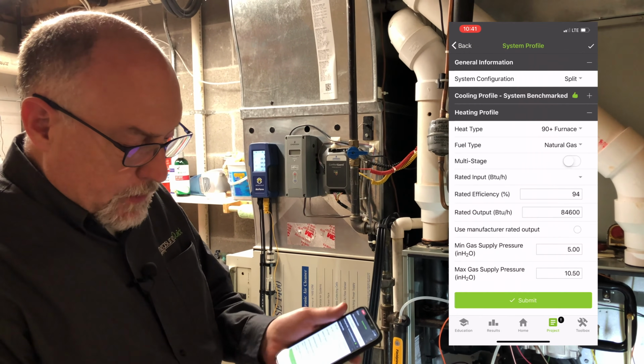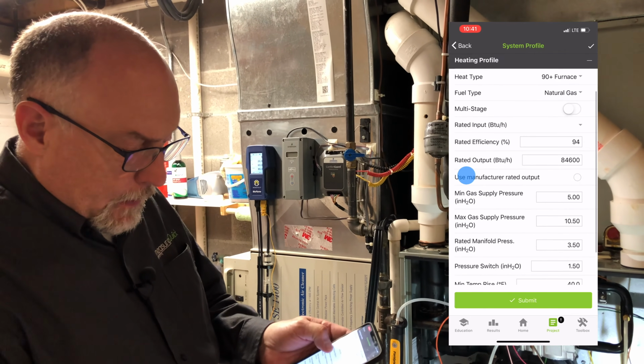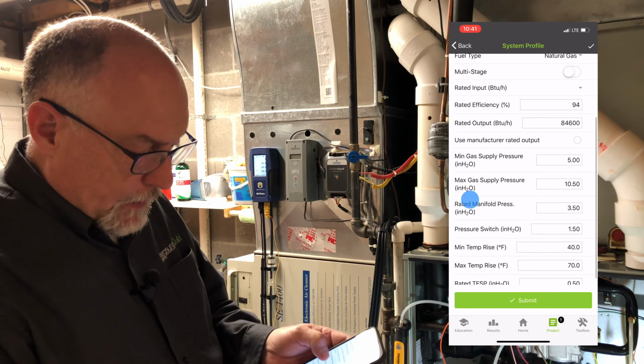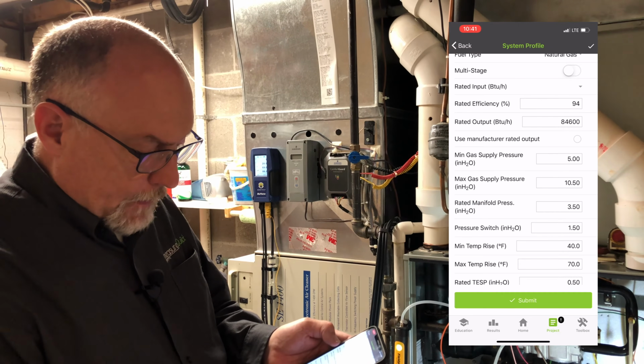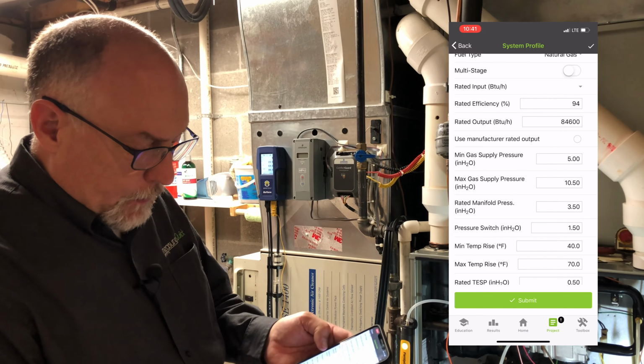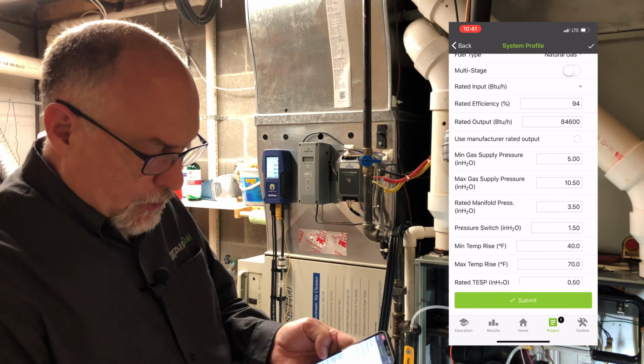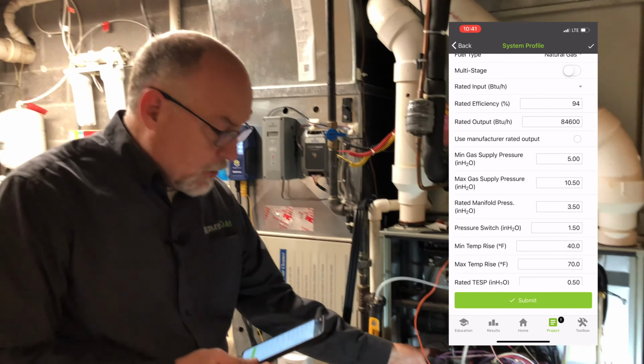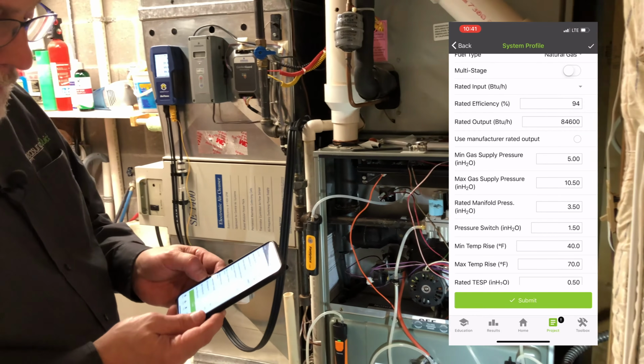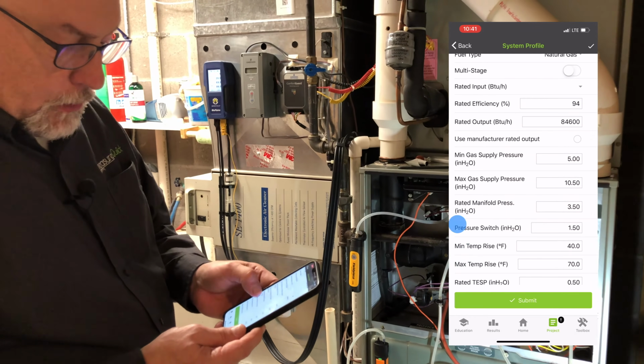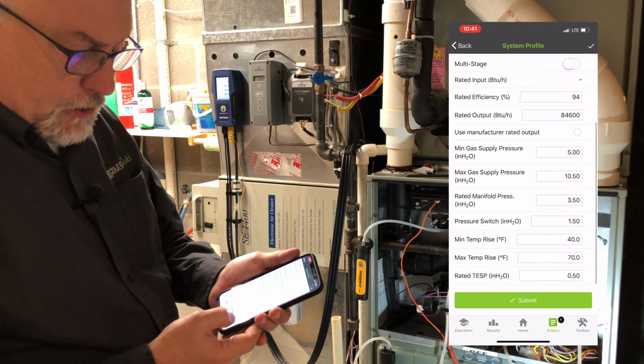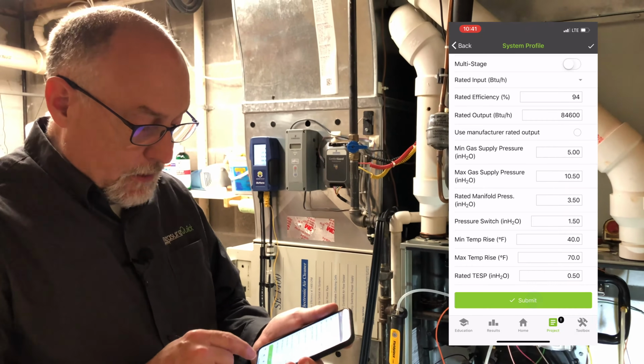So this is a 90 plus natural gas furnace, 94% efficient. It's got a minimum supply pressure of 5, max is 10.5, rated 3.5 inches of manifold pressure, pressure switches, and the high pressure switch is 1.5 inches. Temperature rise is 40 to 70. Total external static pressure is rated at ½ inch. So everything there is good to go. We're going to hit submit.